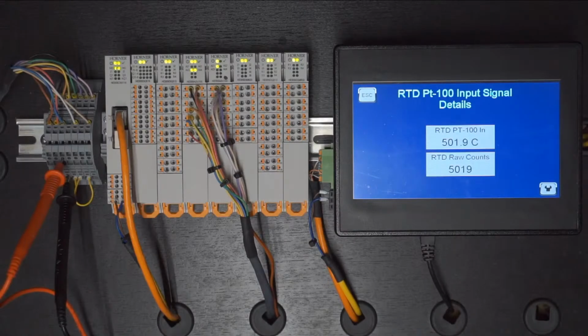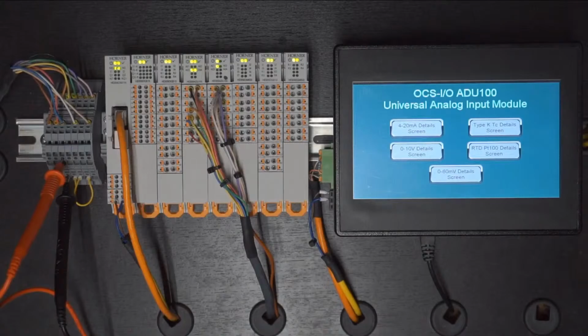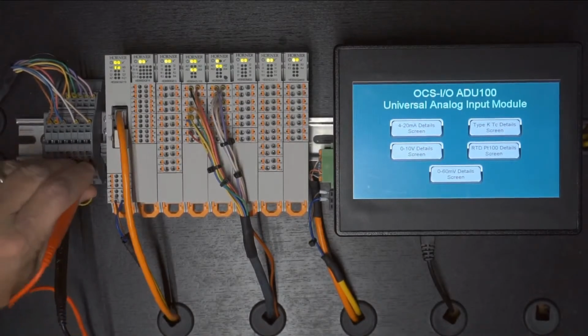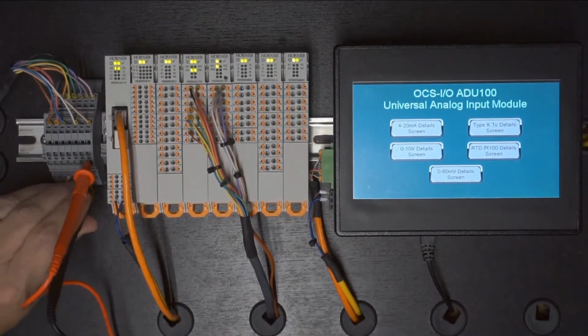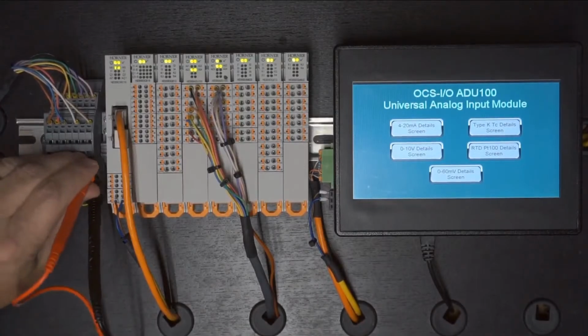So that's RTD. So I have one more range I want to show you, and that is millivolts. So I need to change my simulator from RTDs back to voltage. So let's make that happen here offline. You can't see it, of course. There we go. I'm on voltage. I'm going to set it for, let's say, 5 millivolts. And then I got to remember to move my probe to this last position here. Hopefully I can get a decent connection there.